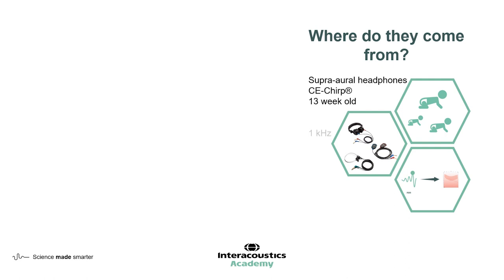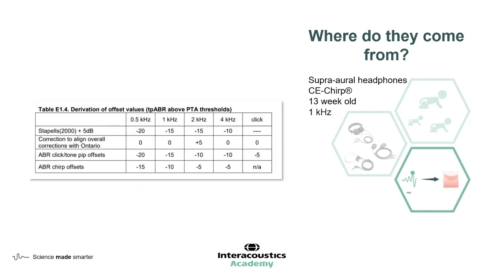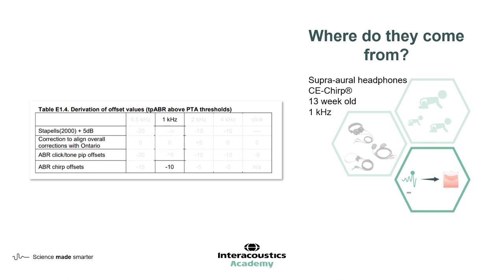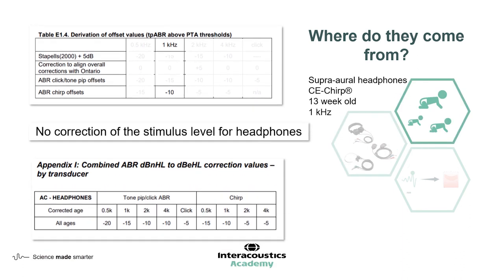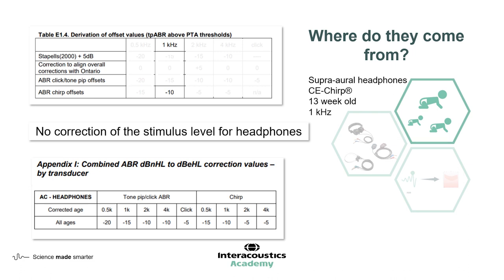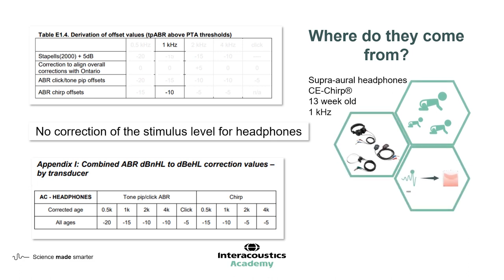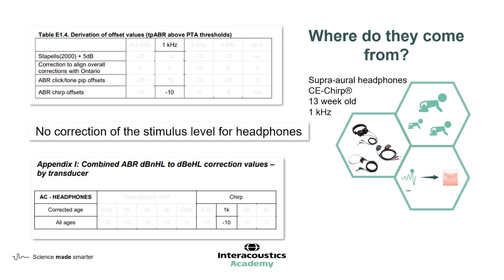Let's consider another example — a 13-week-old using supra-aural headphones, testing one kilohertz CE chirp. First, we need our ABR offset from the Stapells data. We're looking at the one kilohertz column, and we are testing a chirp, so our ABR chirp offset for one kilohertz is minus 10. Next, we need to consider the effect of the transducers — supra-aural headphones. You'll remember that we don't have a correction for the stimulus level of the headphones, and so the headphone data is not divided up into different age bands. The combined correction factor document simply lists the ABR offsets under the headphones section. Because we are dealing with the chirp at one kilohertz, the correction factor of minus 10 matches the ABR offset for chirps at one kilohertz.